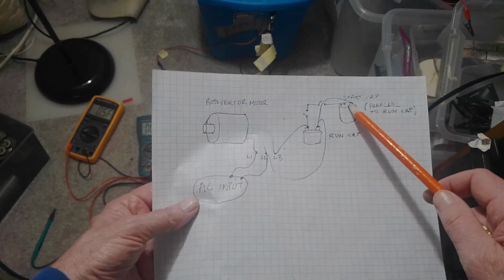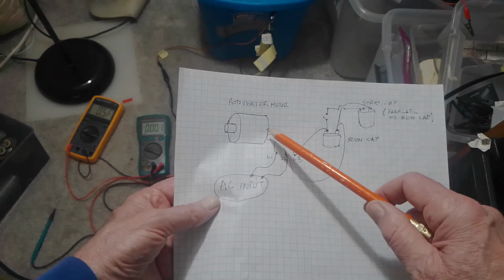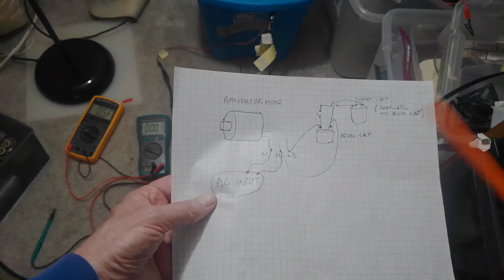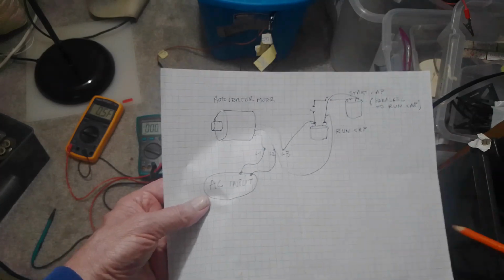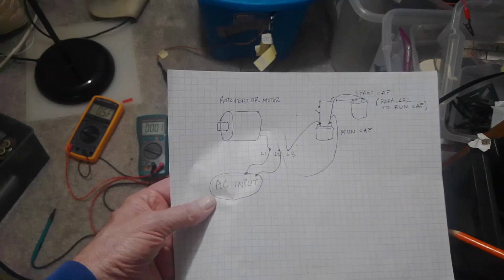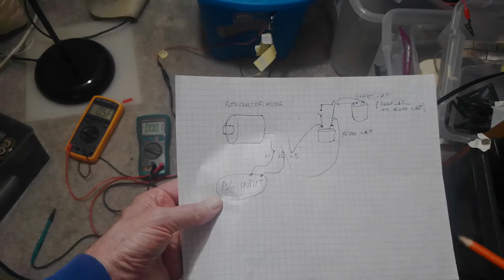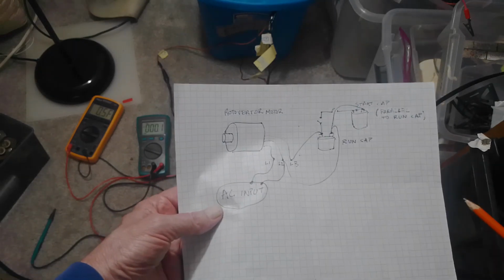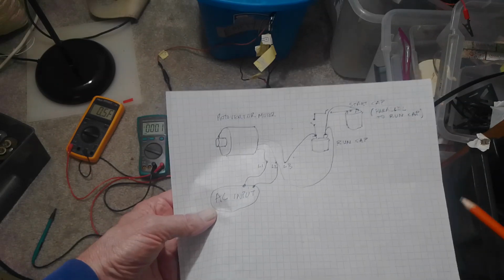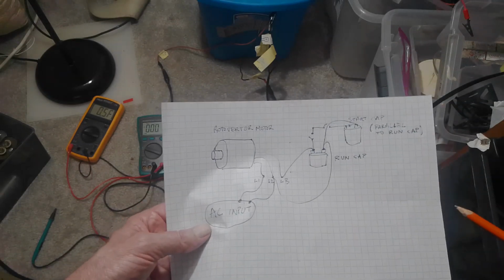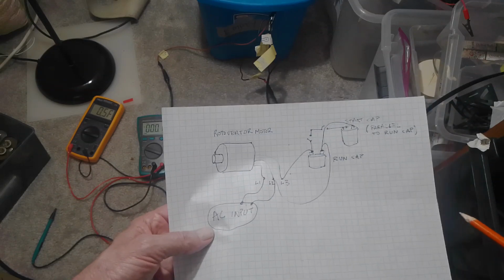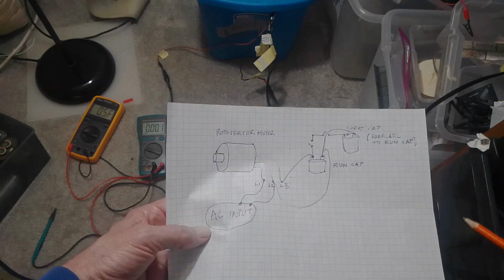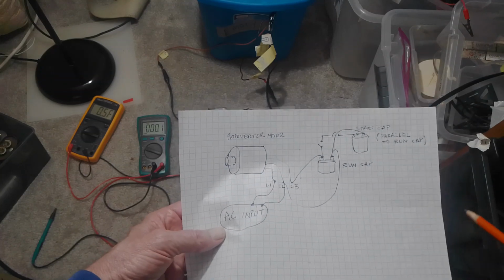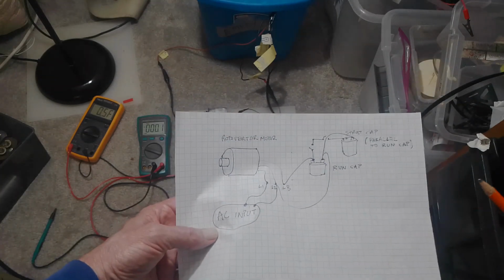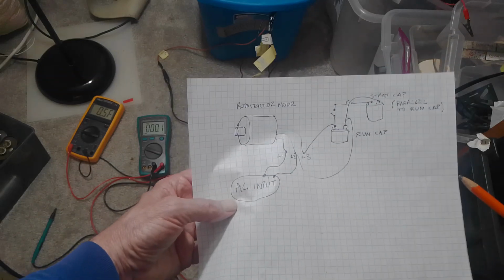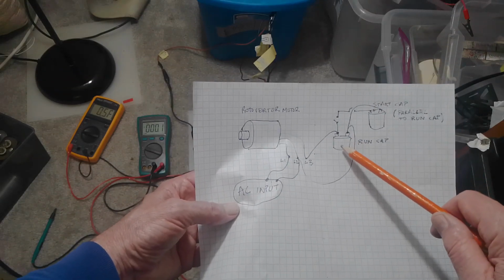And never connect your start cap while it's latched to the sine wave speed running on the run cap, because it'll cause a whole bunch of magnetic braking. And it's possible to actually explode your motor if it's going really fast and you all of a sudden add the start cap, it'll just explode. One guy I know, it leaped off the bench and broke some of his ribs when he put in a start cap while it's in sine wave latch speed.